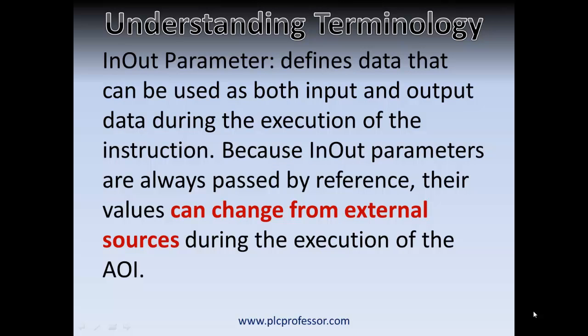A little more on terminology. It is very key that you focus on the difference between input parameter and output parameter versus in-out parameter. An in-out parameter defines data that can be used as both input and output data during the execution of the instruction. Because in-out parameters are always passed by reference, their values can change from external sources during the execution of the add-on instruction.